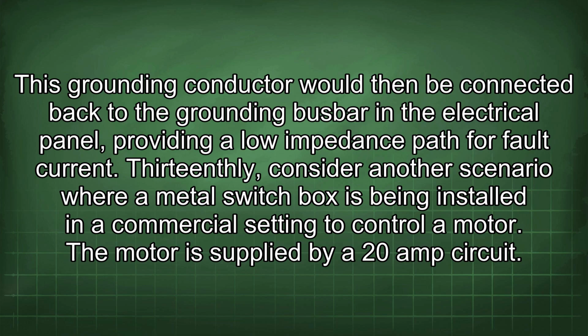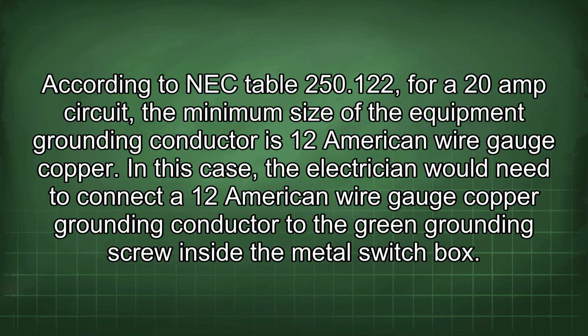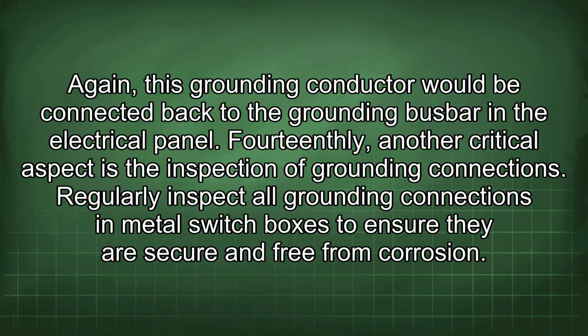to control a motor. The motor is supplied by a 20 amp circuit. According to NEC table 250.122, for a 20 amp circuit, the minimum size of the equipment grounding conductor is 12 American wire gauge copper. In this case, the electrician would need to connect a 12 American wire gauge copper grounding conductor to the green grounding screw inside the metal switch box. Again, this grounding conductor would be connected back to the grounding busbar in the electrical panel.